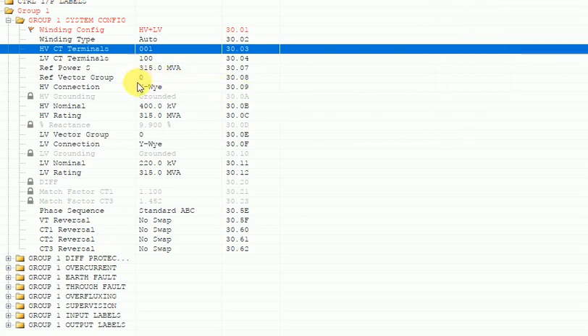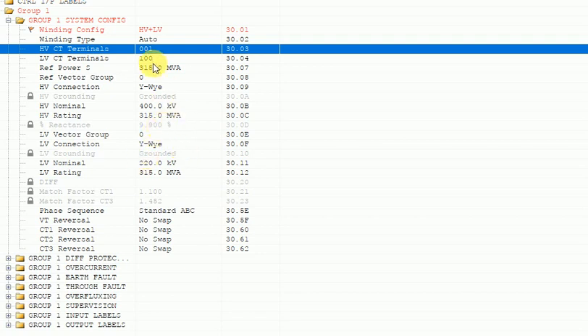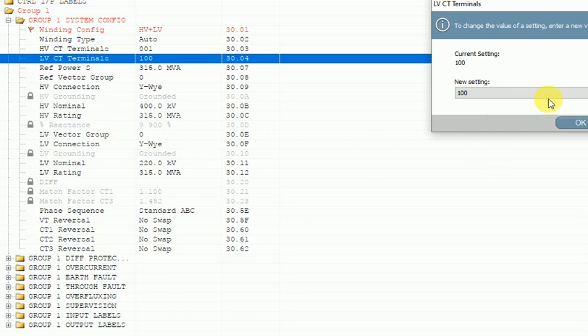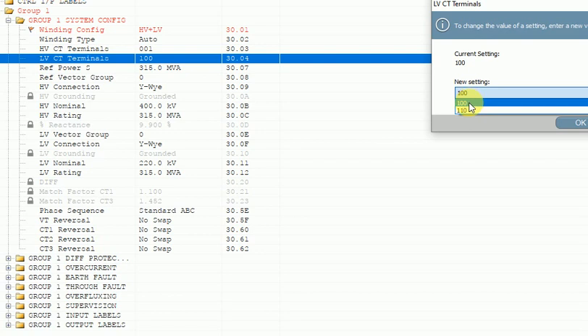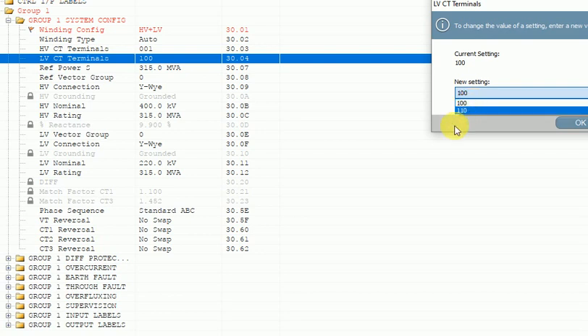Similarly, if you are using two CT summation for the LV CT input in the relay, you have to select 110. 100 means only one CT used for the LV terminal; 110 means two CTs used as LV input in the relay.